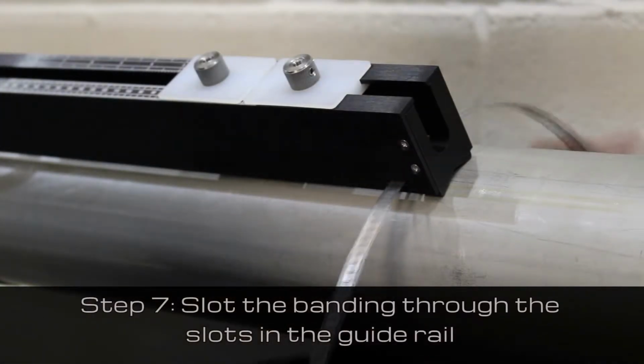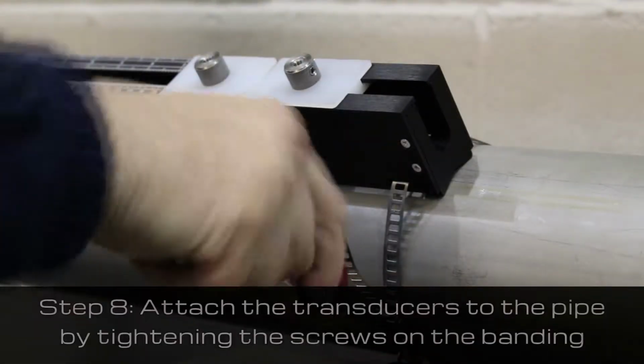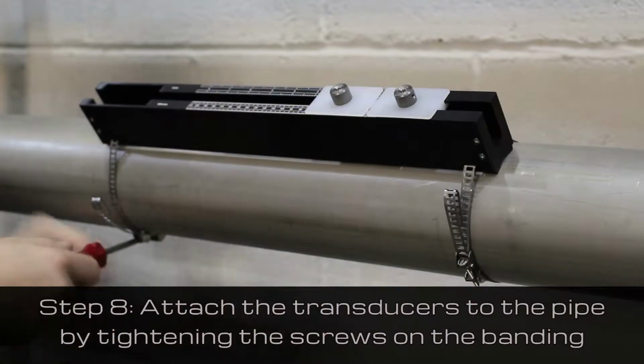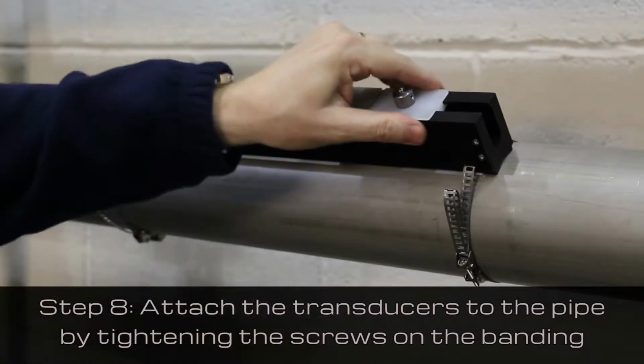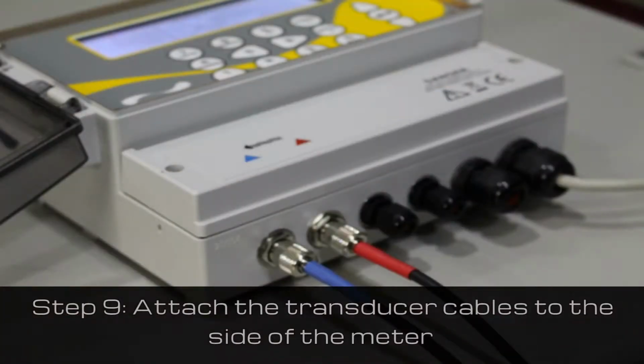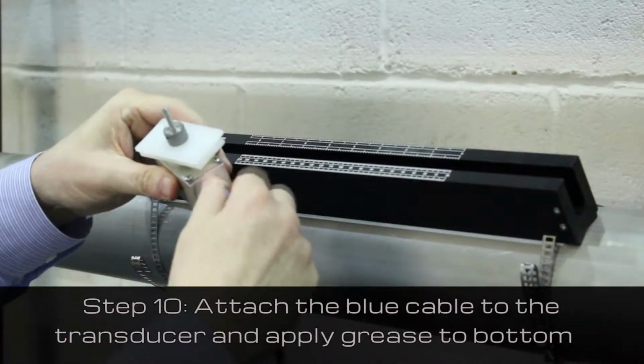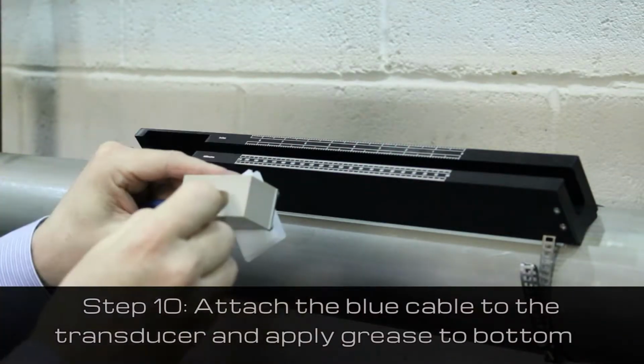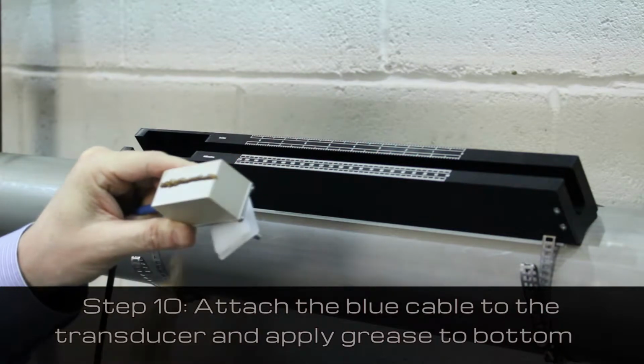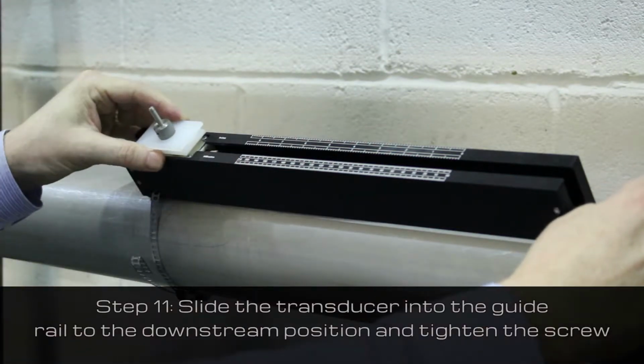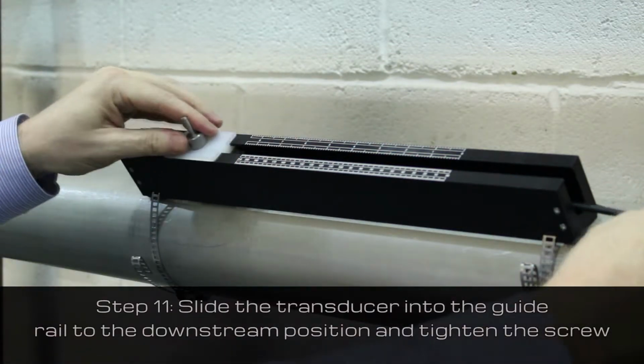Next, fold the banding into the clip as shown. Slot the banding through the slots in the guide rail. Then attach the transducers to the pipe by tightening the screws on the banding. Attach the transducer cables to the side of the meter. Attach the other end of the blue cable to the transducer, apply grease to the bottom, and slide the transducer into the guide rail in the downstream position.